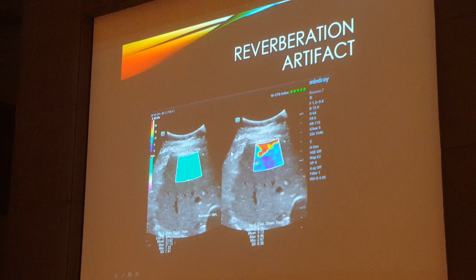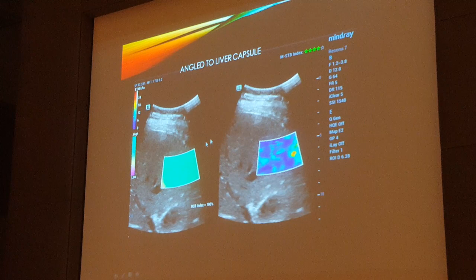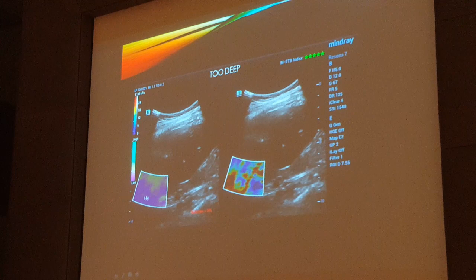And again, you don't want to do angling. Sometimes you can get very high measurements. So here we got at least 4 stars. And although this tells you that we've got good shear waves, we're really doing this as a poor exam, and these measurements are probably inaccurate. So 5 stars in green is not adequate. You still have to make sure everything else is done properly. Again, you don't want to go too deep, and here you can see as we go very deep, we just don't have enough energy to generate shear waves we can measure.